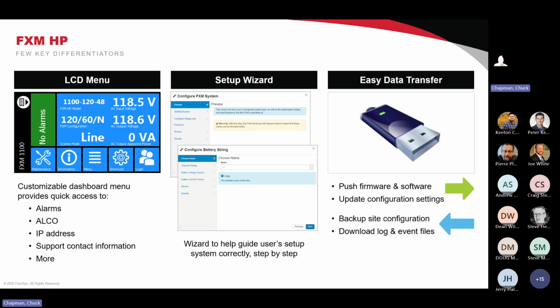It's pretty easy. One of the other great things about the USB port and flash drive is you can push backups and send configs. After going through all the setups—battery setups, everything—you can copy that to a drive and keep it in your pocket. If the site went down a week later, or you need to program another 150 sites, you just take that drive and plug it into the other units. As long as the hardware is the same, everything uploads and it's all set. The only thing you'd have to do at that point is set the IP address information and set the name and location. That's it—it's pretty easy.